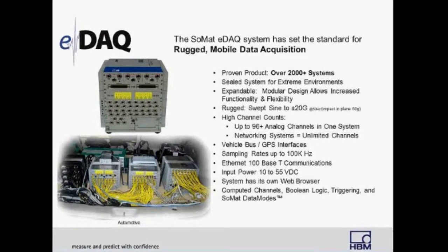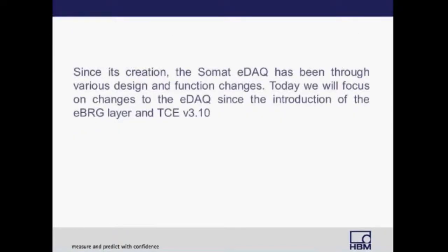By interfacing SOMAT eDAQ with TCE test software, users have the ability to perform acquisitions using various data modes like time and burst histories, event triggering, rain flow, and peak value. The SOMAT eDAQ also has its own self-contained web browser, accessible without the need for TCE software, allowing users to review channels ready to be recorded, start and stop tests, and review and download data. Today we will focus on changes introduced since the eBridge layer in TCE version 3.10.